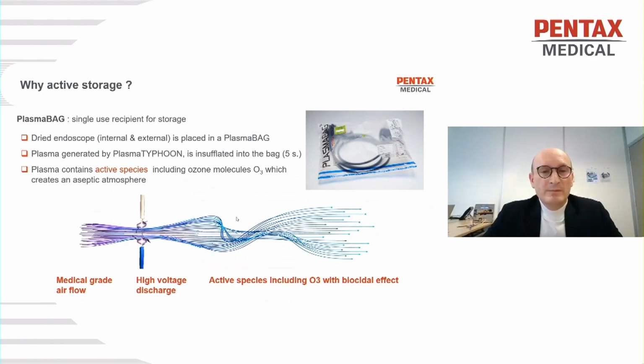We summarize in this drawing how the plasma generation works. We have in the system a medical air flow, which is activated thanks to 2 electrodes creating a high voltage discharge, and active species, including O3, with biocidal effect, are injected inside the bag. What is also important is that the ozone is injected only in the bag and is not harmful for the user, who is outside. The ozone will act, and after 5 minutes, it will recombine into oxygen.